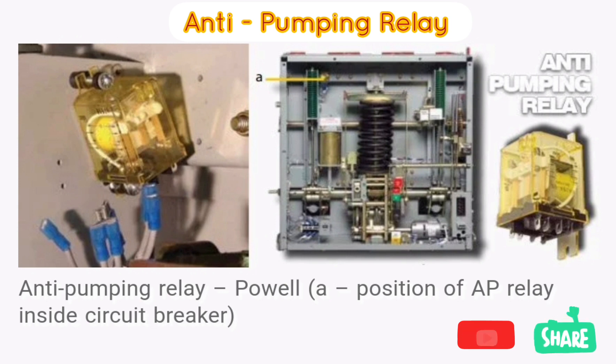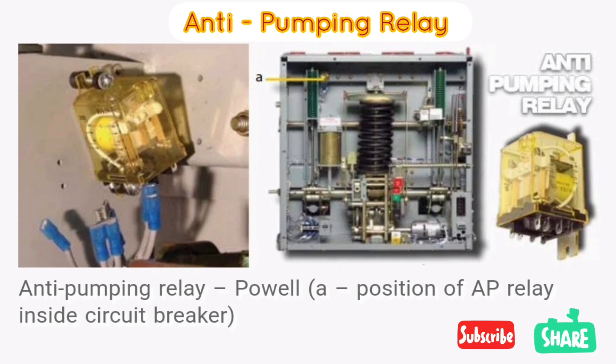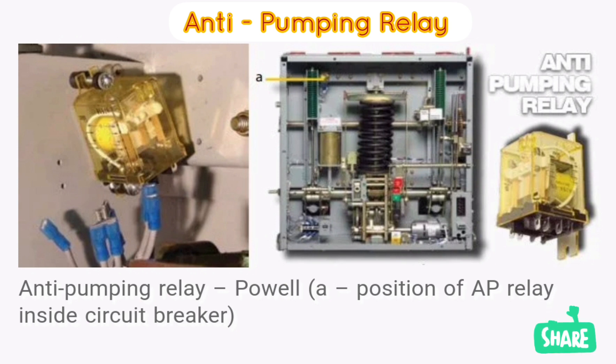This video describes the anti-pumping relay, its definition, function, and circuit diagram. In a circuit breaker, it is desired that when close and trip operation is performed on the circuit breaker with the closing coil energized, the subsequent closing operation should be prevented. So let's begin with the basic introduction of the anti-pumping relay.